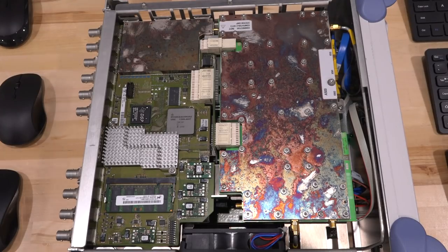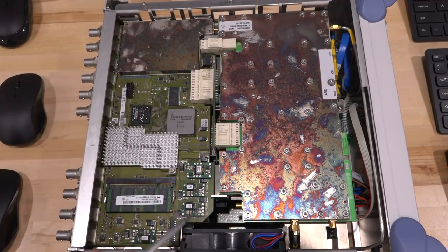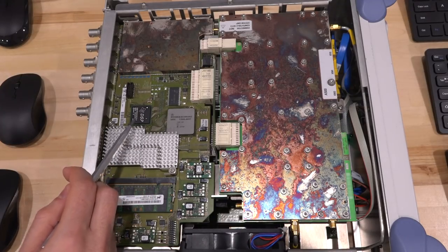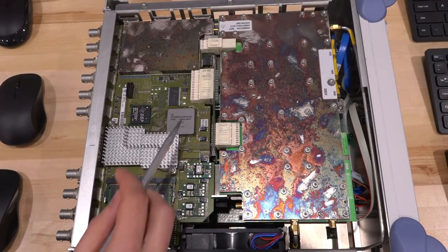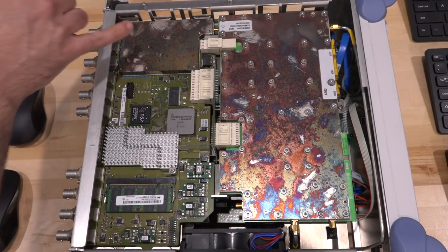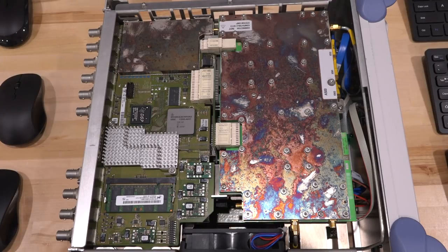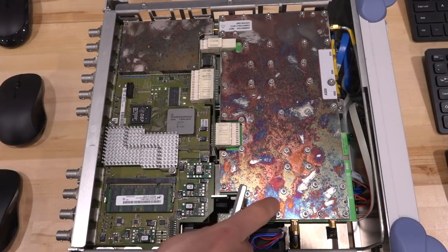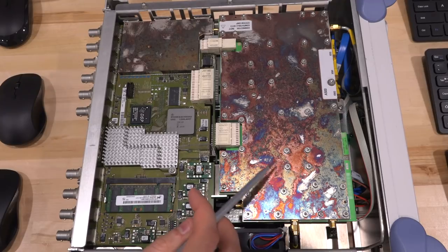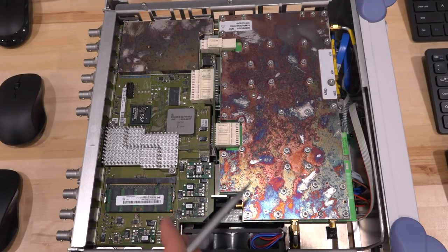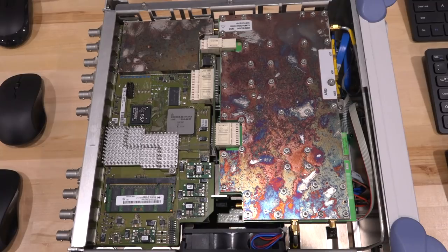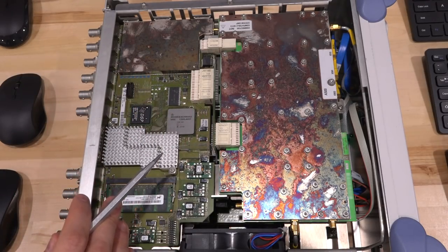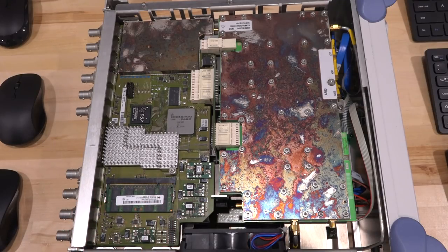And here is the top of the unit with the cover off and we can already identify the different boards that are in here based on the block diagram we saw. So here's the baseband section. You can see there's a custom Rohde & Schwarz IC here, DSP from TI, some blocks could be FPGAs of some kind, memory, almost certainly the ARB storage memory, DC-DC converters, interconnect to the main bus. This shield area over here is almost certainly the analog portion of the baseband generator and you can see it couples onto the main modulator board here. This discoloration you see on the surface of the metal is normal. This is just the surface reacting. It doesn't really matter. This is a fairly thick piece of metal. It has nothing to do with the inside of the chassis there. I think we should flip it to the other side. None of these boards are a problem and even if they are a problem we haven't even tested them because the problem is from the output. So we have to look to the other side.